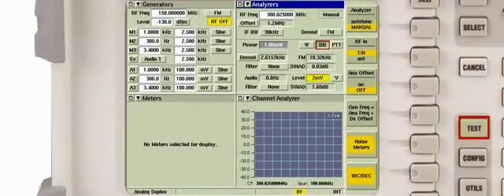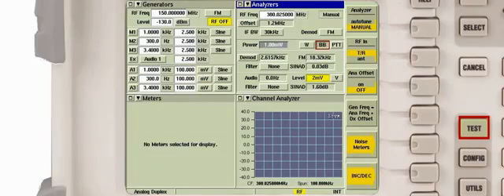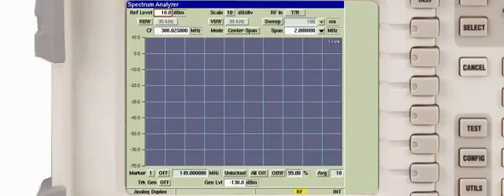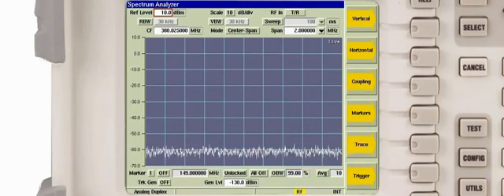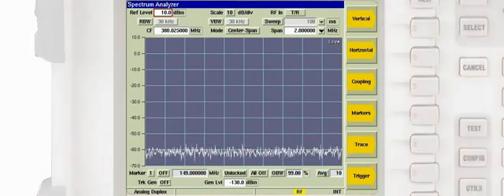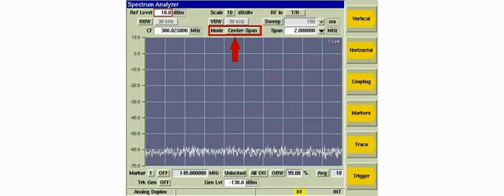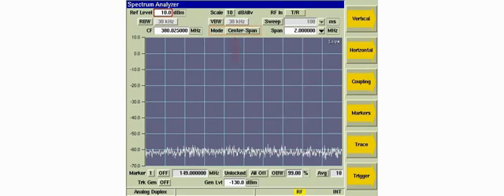We begin by pressing the test key to access the spectrum analyzer. We'll sweep the cable from 100 MHz to 1 GHz. To do that, we'll set the frequency mode to start-stop.